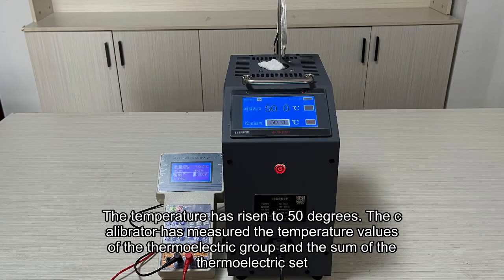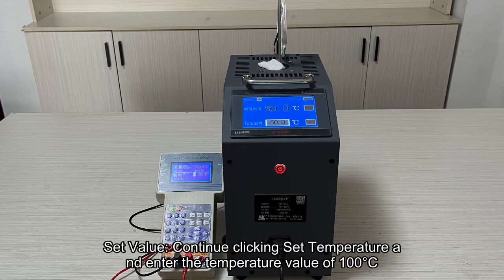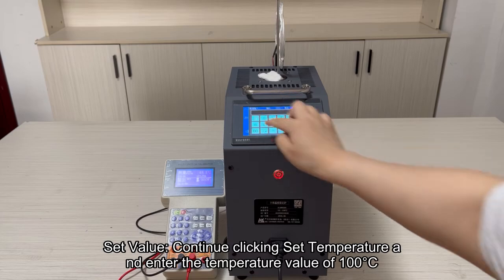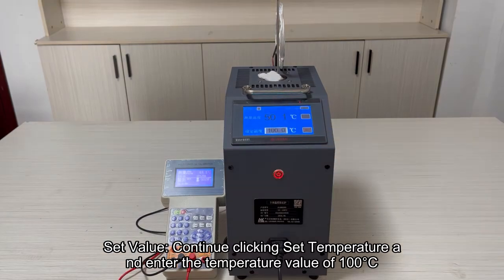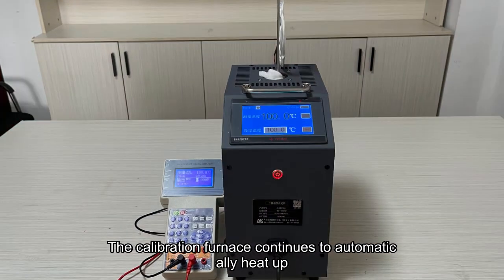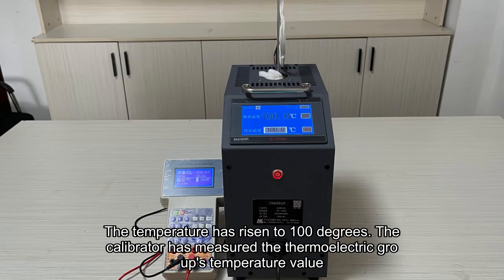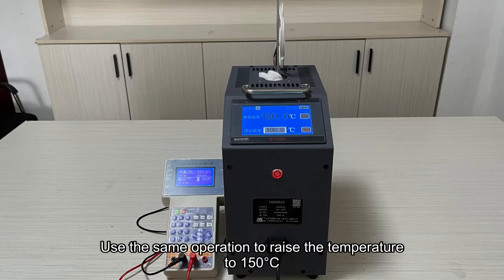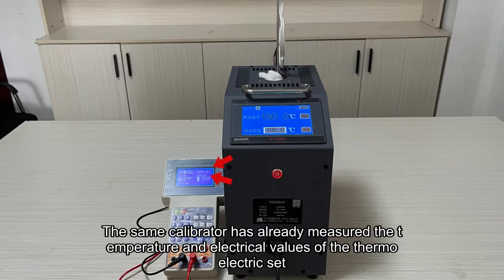The temperature has risen to 50 degrees. The calibrator has measured the temperature value of the thermal resistor and the set value. Continue clicking Set Temperature and enter the temperature value of 100. The calibration furnace continues to automatically heat up. The temperature has risen to 100 degrees. The calibrator has measured the thermal resistor's temperature value. Use the same operation to raise the temperature to 150. The same, the calibrator has already measured the temperature and electrical values of the thermal resistor.